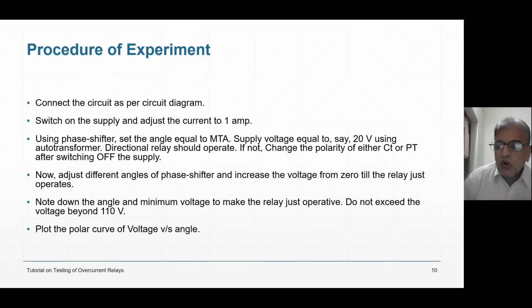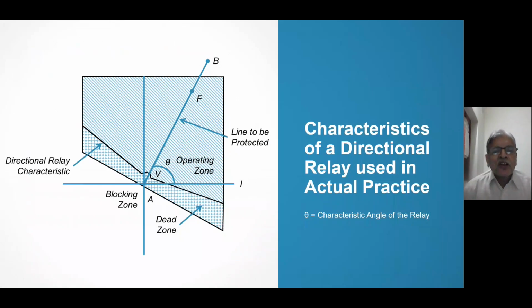Once you have done that, plot the polar curve. Polar curve means this curve. This is our directional relay characteristic, right? Angle theta is say 60 degree. I have given, matlab some manufacturer has given me theta is equal to 60 degree. So that line from I axis, reference axis, is known as the maximum torque line. Line to be protected, if you want to say, if line is at 60 degree, line is usually at 75 or 80 degree.